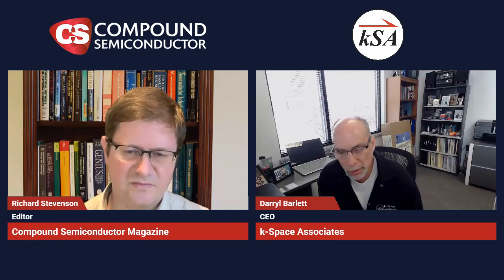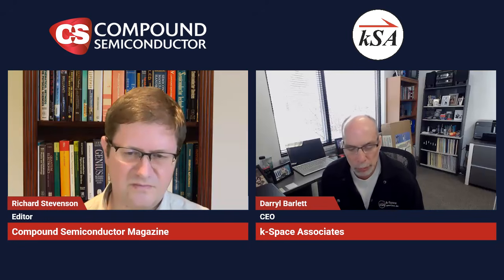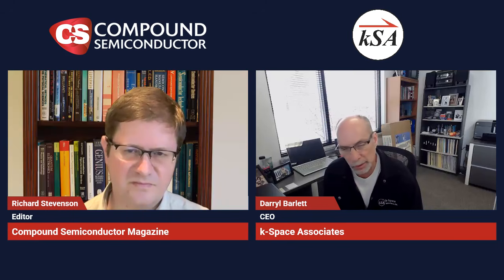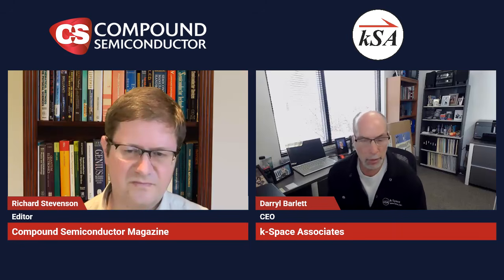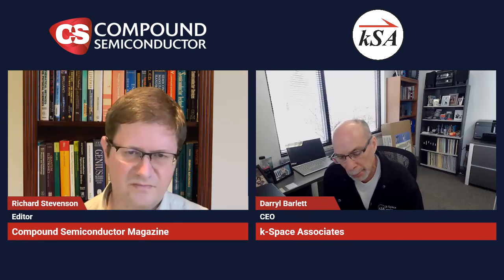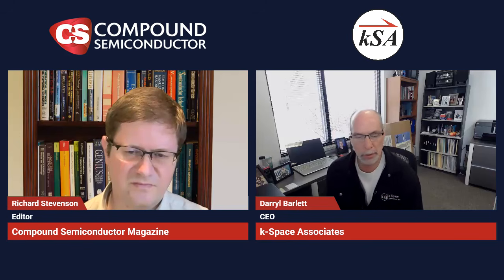And that's where our KSA Bandit tool has really been of great use to folks during thin film deposition, mainly in MBE, sputter processes, and secondarily MOCVD, where we can optically and accurately measure the wafer and the film temperature, typically down to a few tenths of a degree. And the Bandit system now has multiple temperature measurement capabilities.